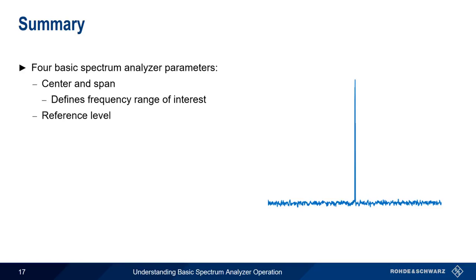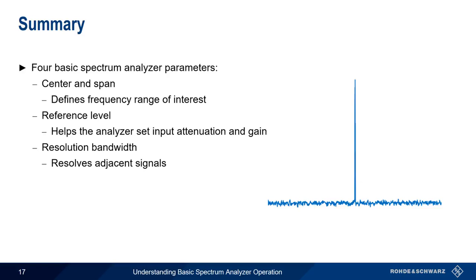Aside from keeping the trace on the display, reference level also helps the analyzer choose appropriate values for input attenuation and gain. Although it's not usually hard to decide which values to use for center, span, and reference level, choosing resolution bandwidth involves making some trade-offs. Lower resolution bandwidth helps separate closely spaced signals, and reduce the noise floor or DANL, but they also increase sweep time.